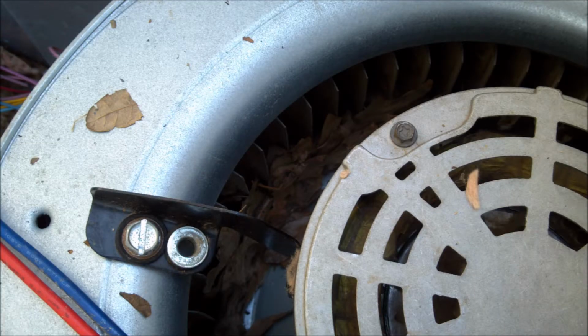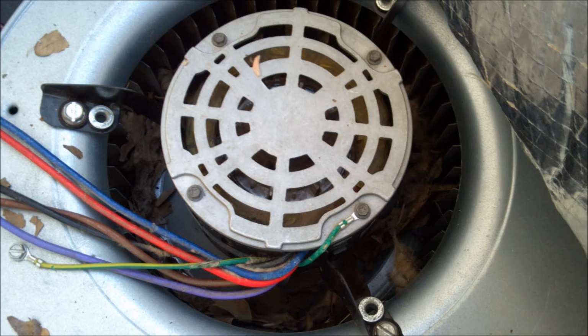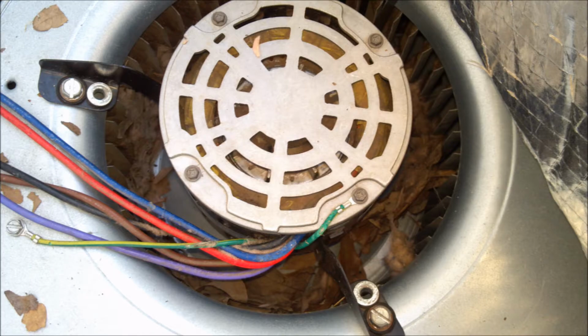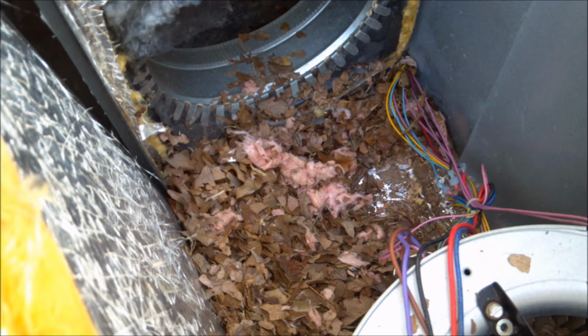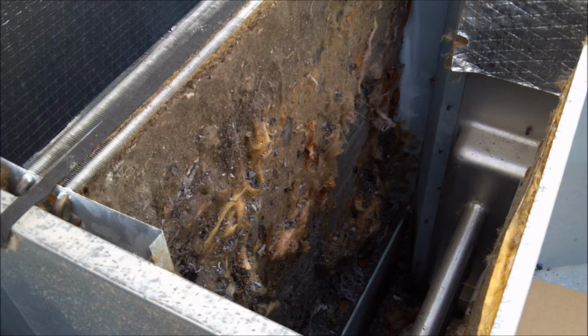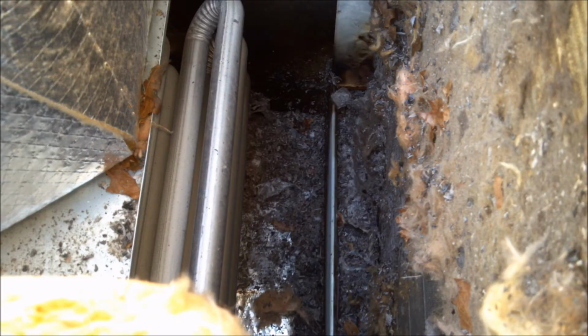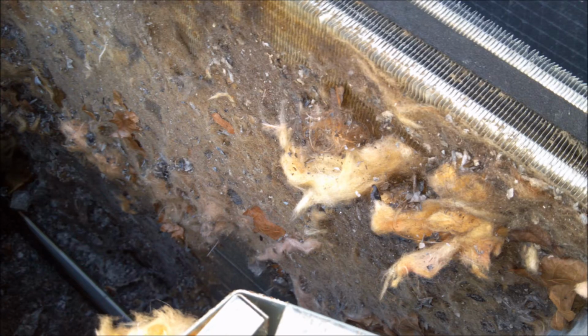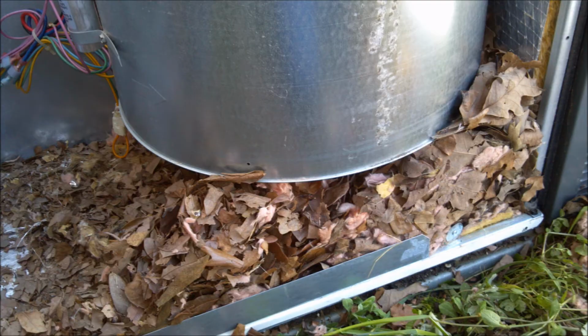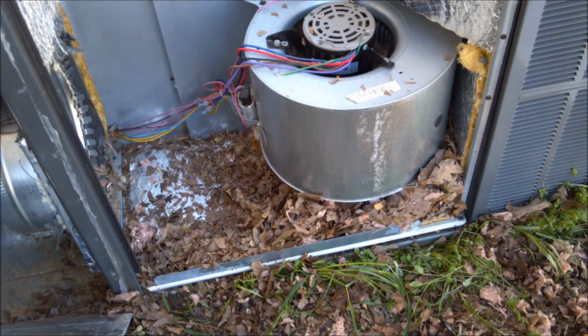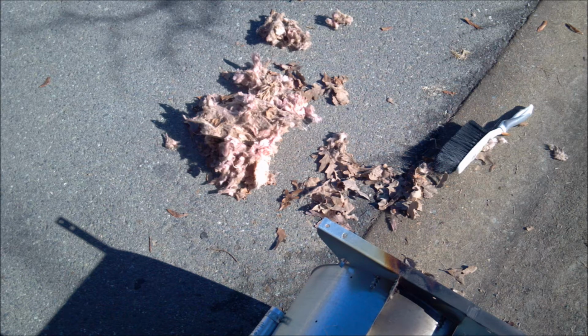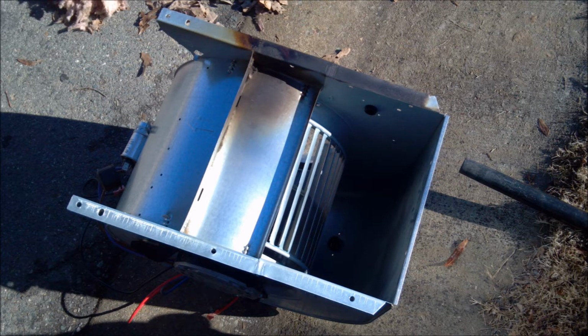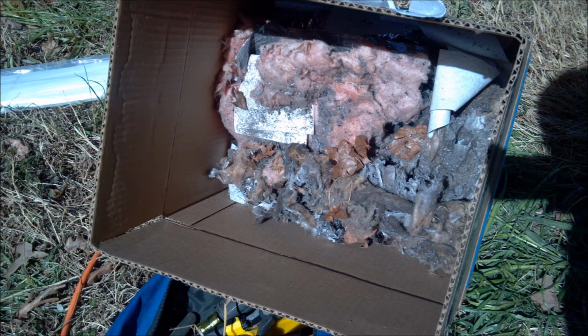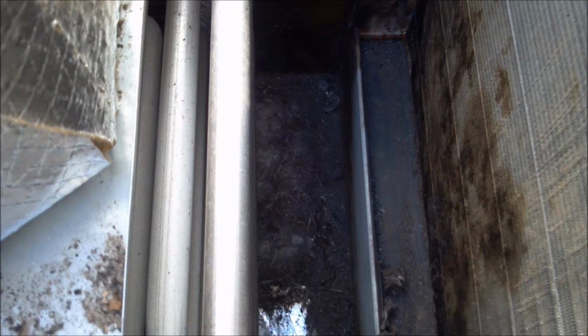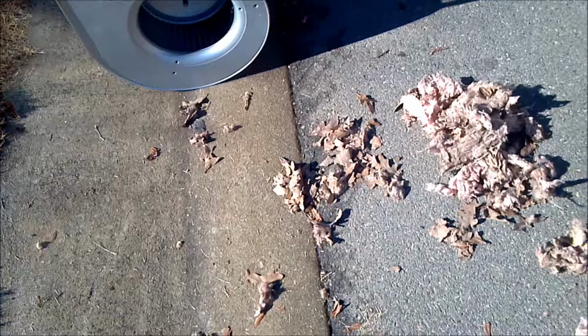So here are just some pictures of the fan with the leaves all in it, and the insulation, leaves in the compartment, the debris on the coil, ashes in the bottom, more debris. Look at all the leaves underneath that fan. It was just packed in there. And there's where all the stuff was that was in the fan that had to be pulled out. And this was all off of the evaporator coil. Now it's all cleaned up there. Just got to clean out a little bit of ashes left.